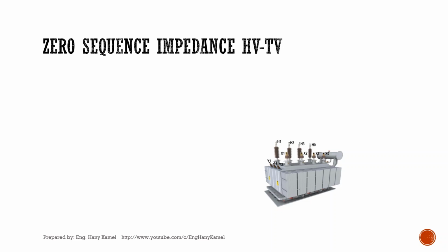This test is important to check if there is any deformation in the windings or connections or core structure. The vector group is very important, as this test can only be done from the star with neutral side. Our example power transformer has vector group YNYND11 and tertiary closed delta with 3 bushings.